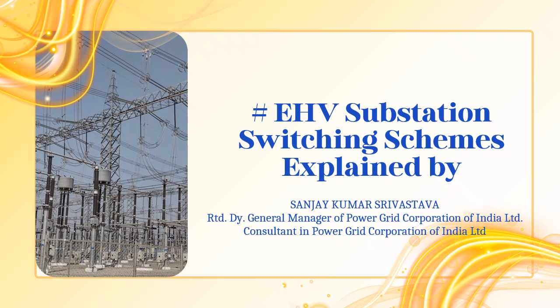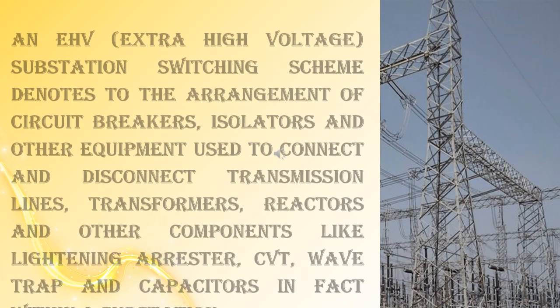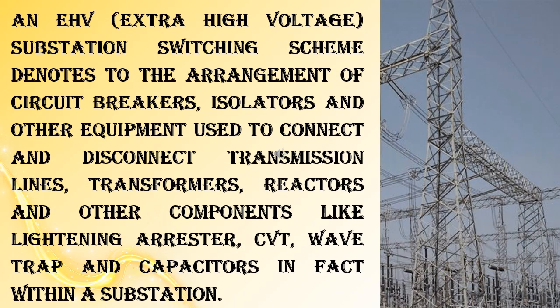EHV substation switching schemes. An EHV (extra high voltage) substation switching scheme denotes the arrangement of circuit breakers, isolators and other equipment used to connect and disconnect transmission lines, transformers, reactors and other components like lightning arresters, CVT, wave trap and capacitors.